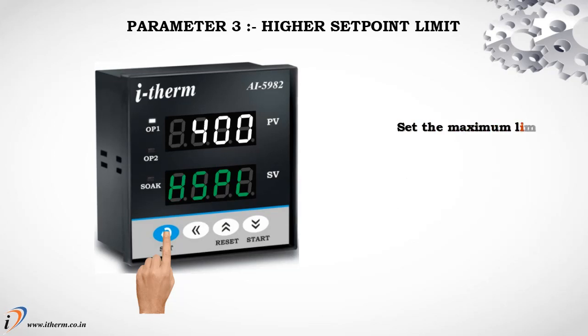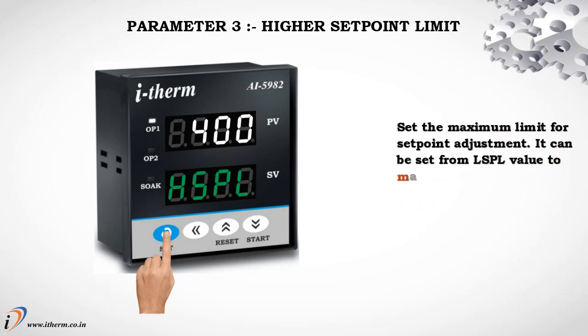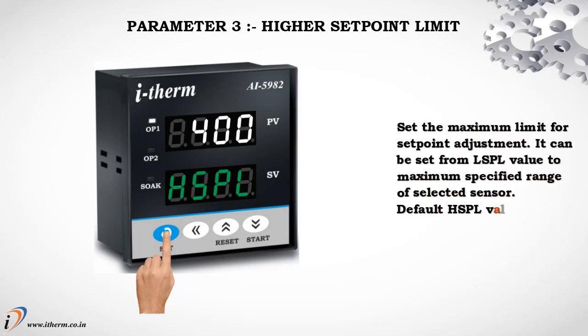Parameter 3: Higher Set Point Limit (HSPL). Set the maximum limit for set point adjustment. It can be set from the LSPL value to the maximum specified range of the selected sensor. Default HSPL value is 400.